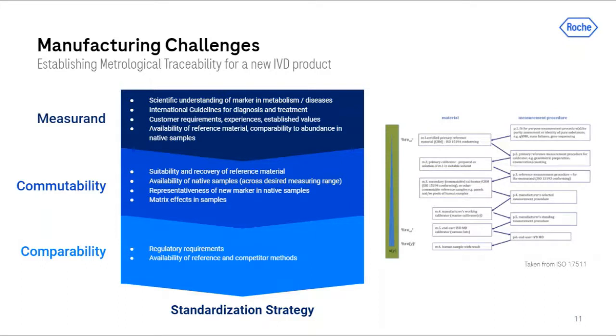At the beginning of an IVD development, one has to obtain a broad scientific understanding of the measurand to be detected — for example, the role it plays in the human body, its synthesis or uptake and metabolism, and its abundance in various associated diseases. One also has to understand the history of the measurand: are there already international guidelines or customer expectations for expected values? Is there a reference material or reference method available? This should set the starting point for standardization — the definition of the measurand and potential reference materials or methods.